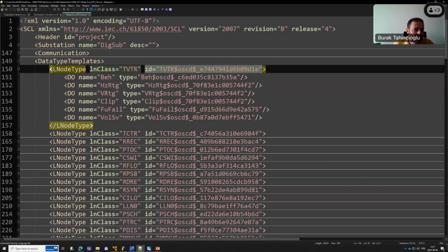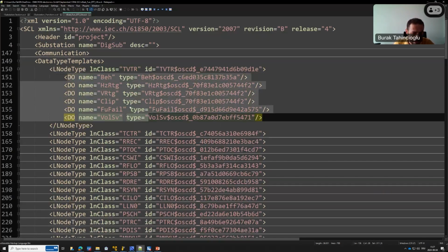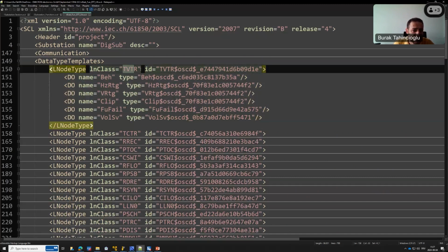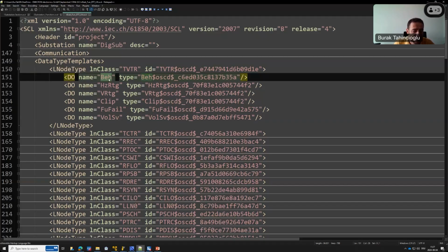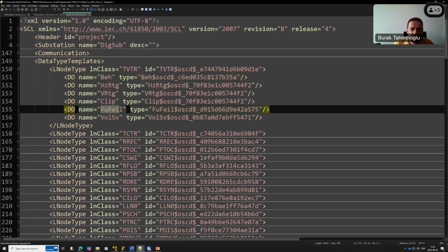And under the logical node type, you have the data objects. For instance, this is a TVTR. The ones that you know what's a TVTR - this is a voltage transformer logical node, which would have anyway a behavior because it's mandatory, but something else as maybe the sampled values, maybe the fuse failure, and something any other thing.